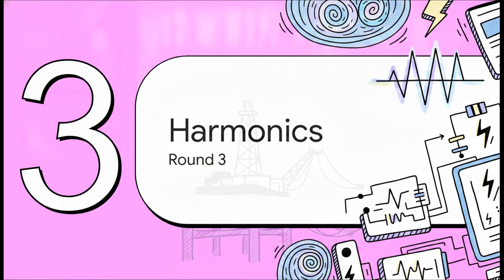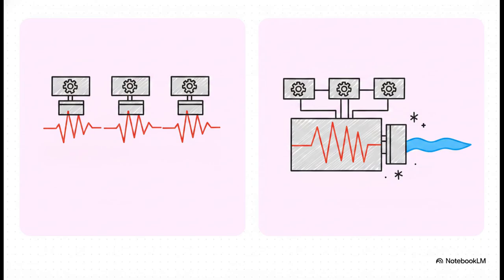Which leads us to round 3, electrical cleanliness and harmonics. You see, physical space isn't our only constraint out there. We also have to actively manage the electrical environment. Rectifiers inherently draw current in pulses, and that creates harmonic distortion. In a single drive system, every independent rectifier is drawing its own distorted current straight from the switchboard. That makes bulky harmonic filters mandatory on practically every single unit. But multi-drive? It centralizes all that distortion at one common rectifier.